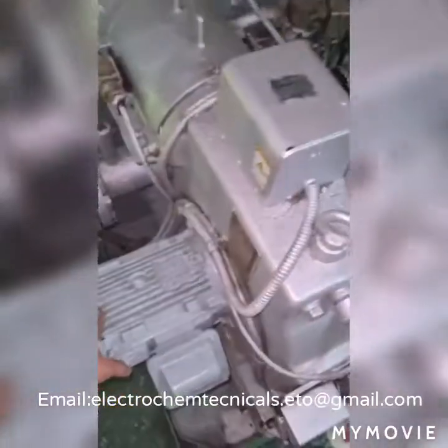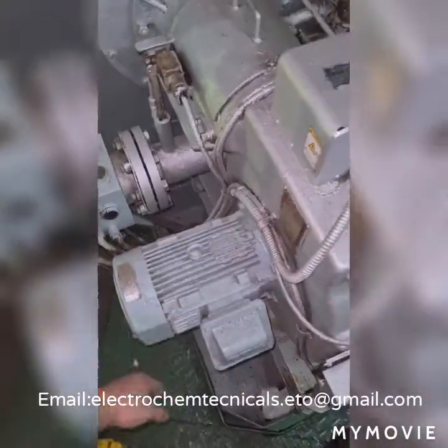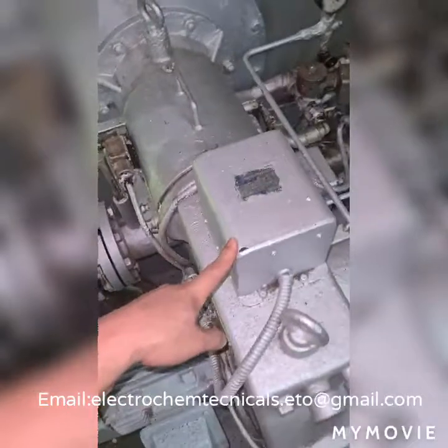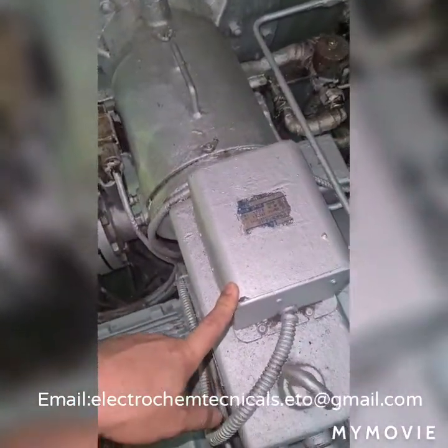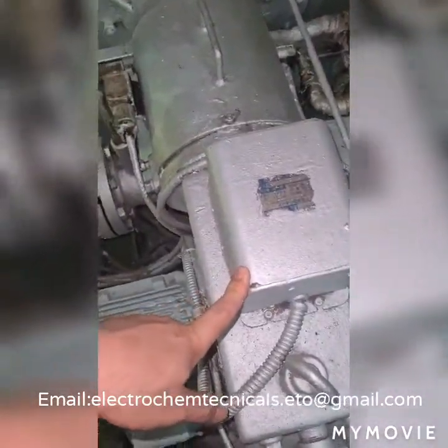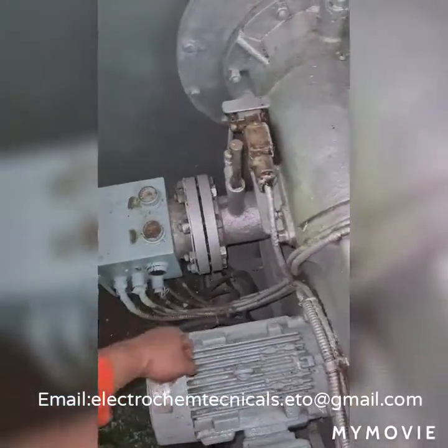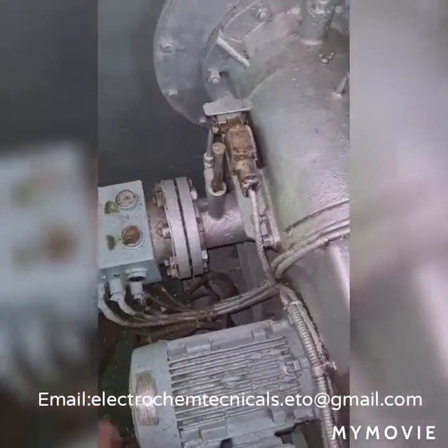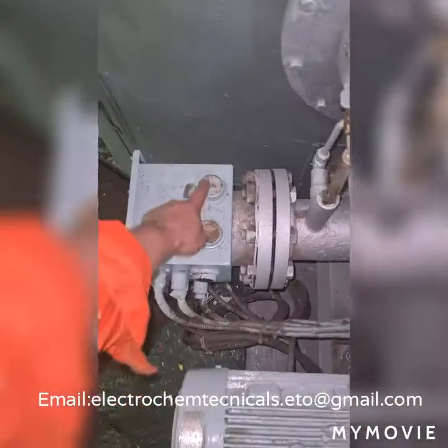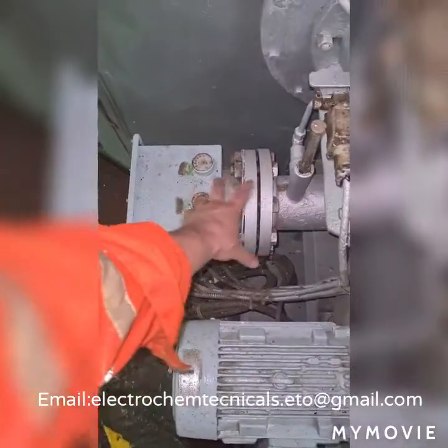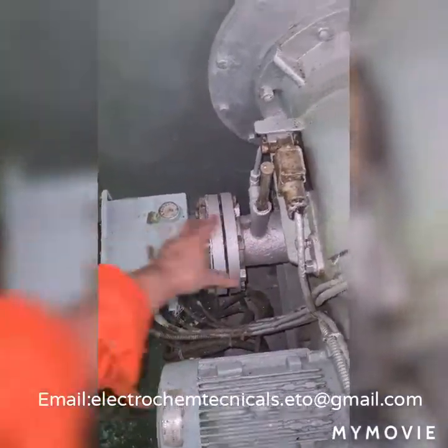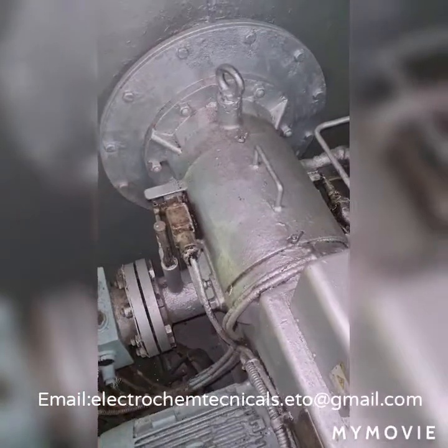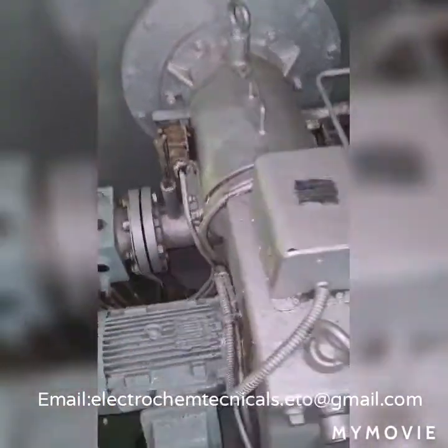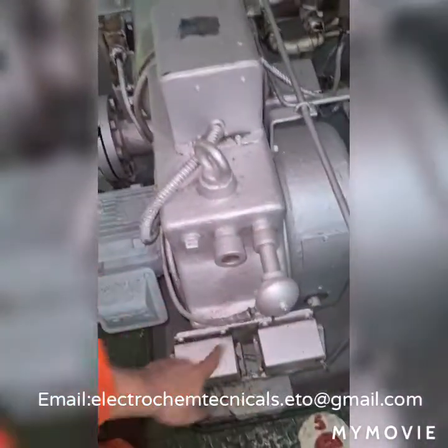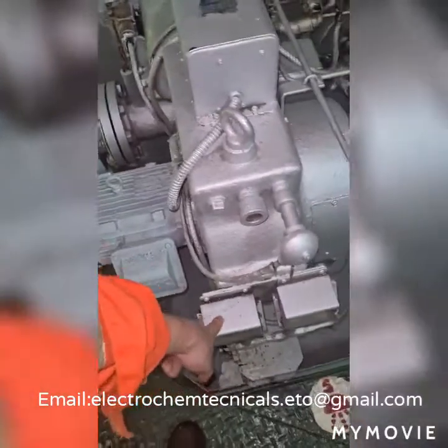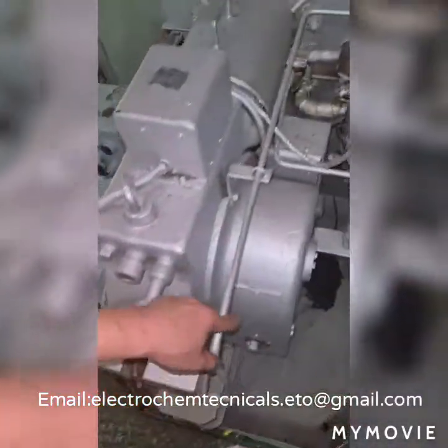This is the forced draft fan. This is the ignition transformer operating at about 14.5 kilovolts. This is the limit switch. This is the thermostat from which the electric heater heats up the fuel going to the boiler. These are the two pressure switches to monitor the fuel inlet pressure.